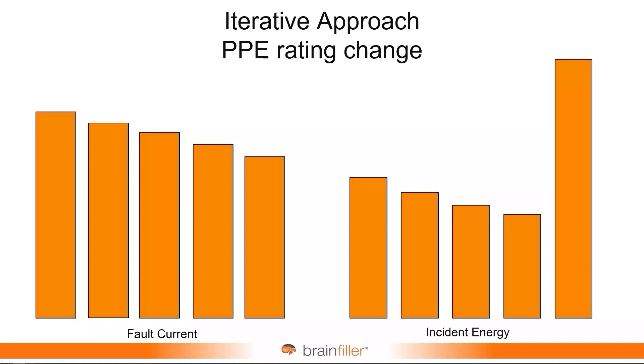What you've done is you've defined a range of fault currents where the PPE that you want to use is acceptable, and you've identified how low this can go before you start to have trouble with device operation. Not a perfect answer, but at least it'll give you a range.